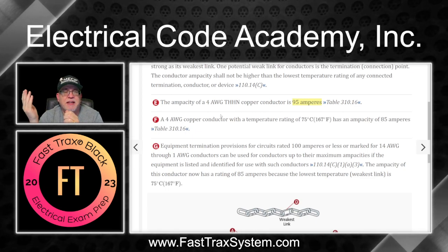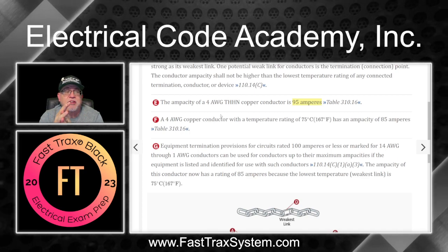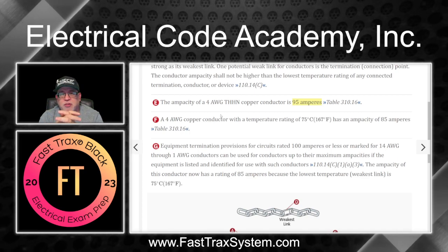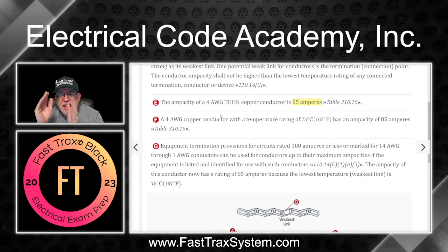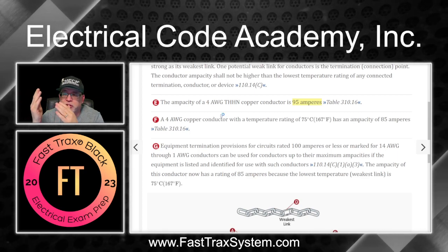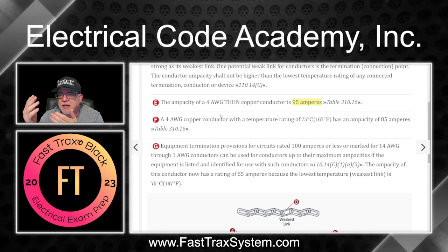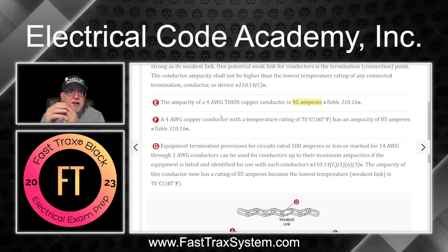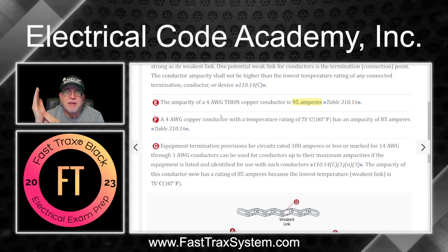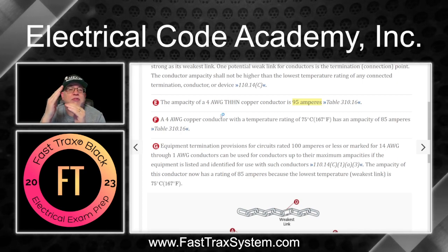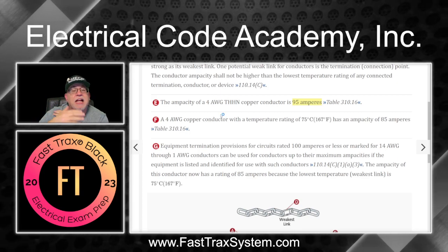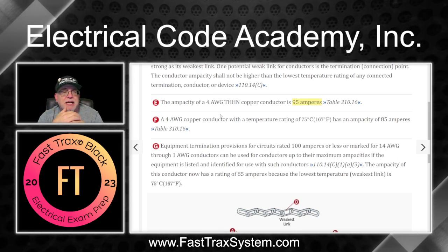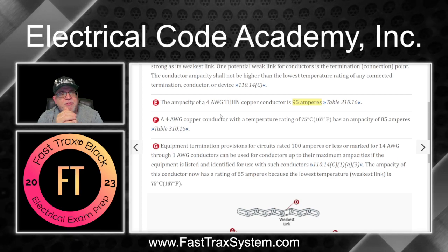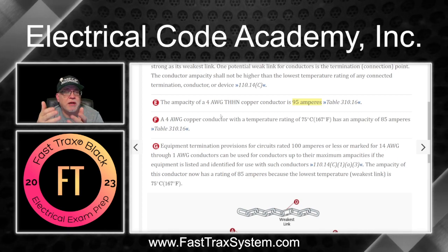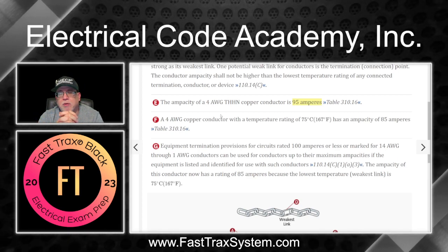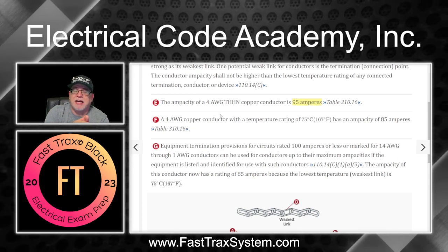So all we did is make sure that we have a conductor that's still adequate for the values under the 75-degree column. Now, if I had done an adjustment for a number of current carrying conductors, let's say 8 current carrying conductors, starting from the 95, and it dropped me below the 85, then we would have a problem. We'd have to look at our calculated load and see what it is in that scenario, and then we might have to up our conductor size.